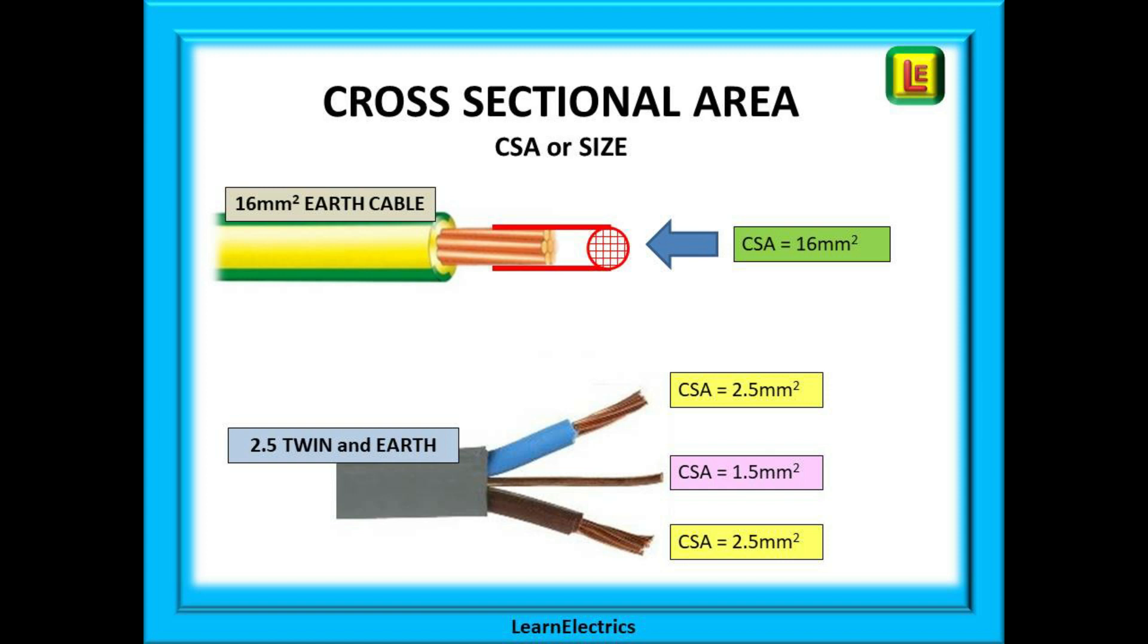We mentioned the size of the cable. We should really say the cross sectional area or CSA. This is not the same as the diameter of the copper. It is the area of the cut surface and it is measured in square millimeters but we often just say 10 mil or 6 mil instead of saying 6 millimeters squared and so on.